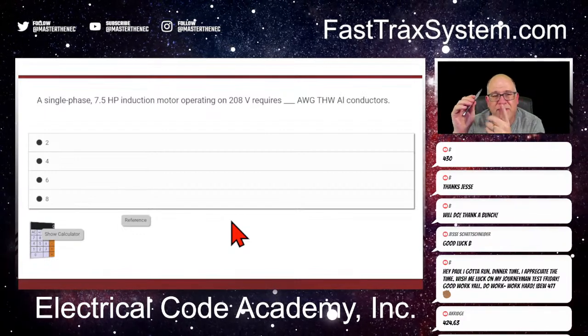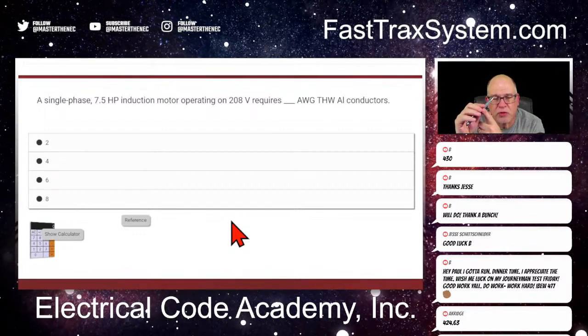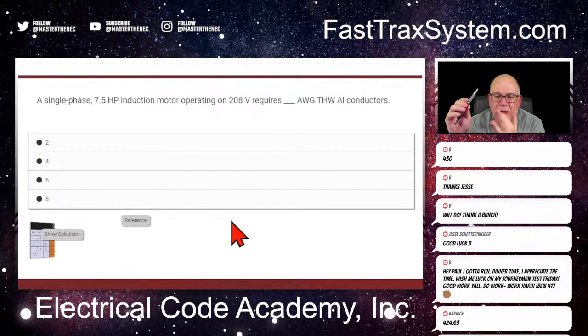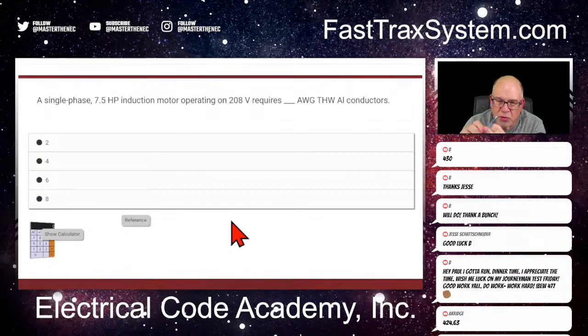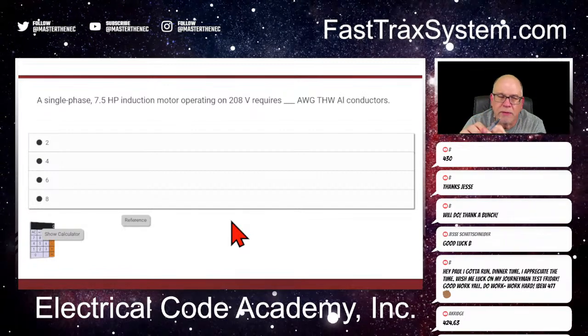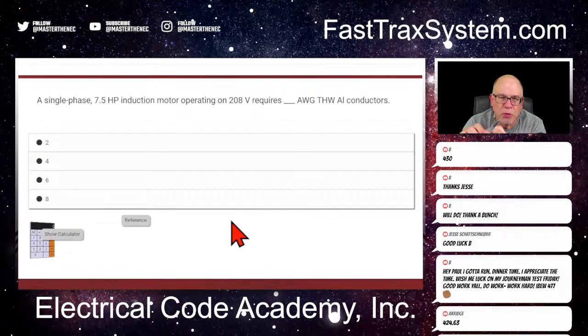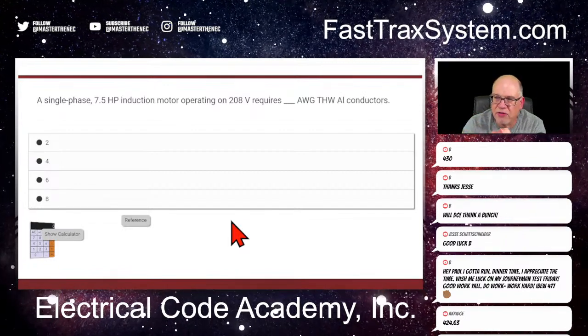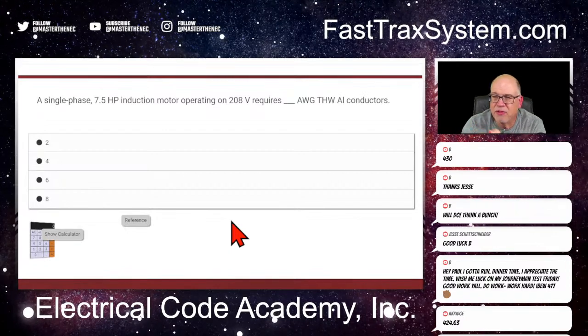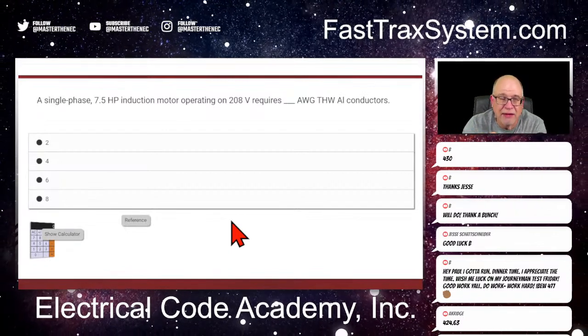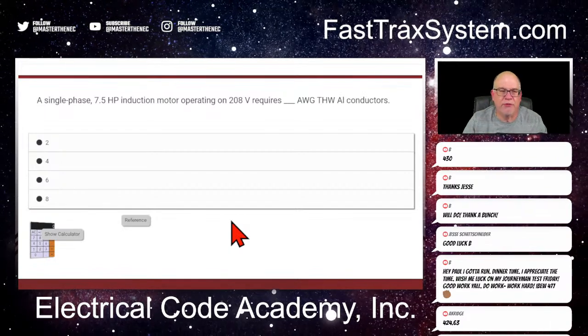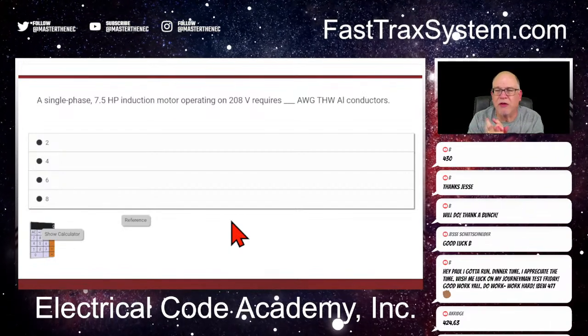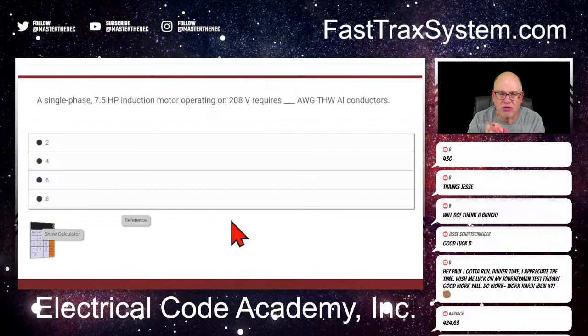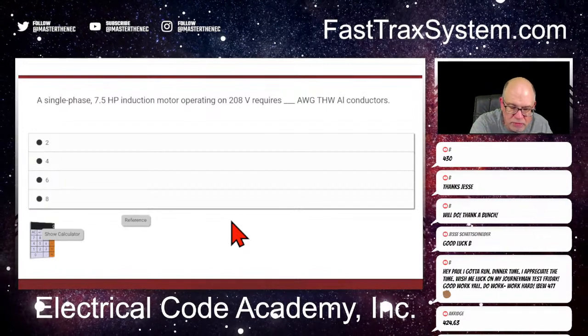Of course, you also have for locked rotor, 430.251 and all that too. But for standard, normal type motors, what we're looking for is 430.248, 249, 250, depending on whether it's single phase or 3-phase. Obviously this is single phase, 208 volt. So it's being derived from a 3-phase, but we're working with a motor that is single phase, 208 volt.